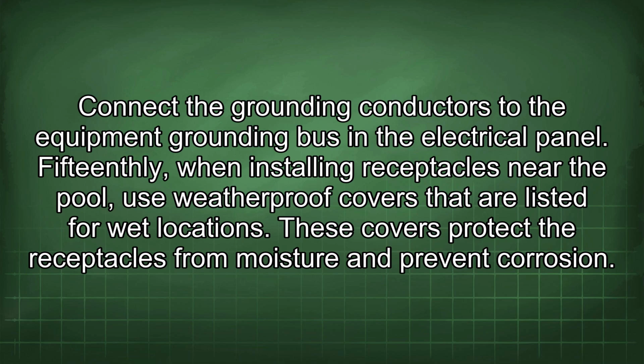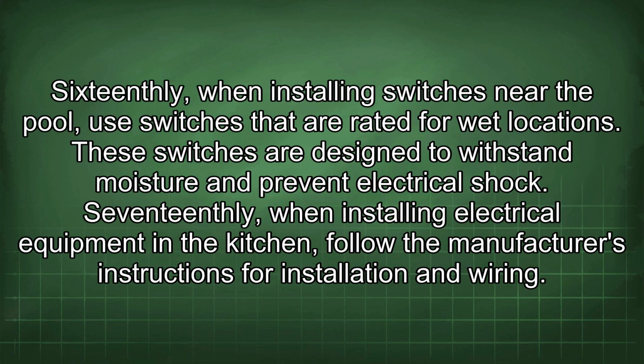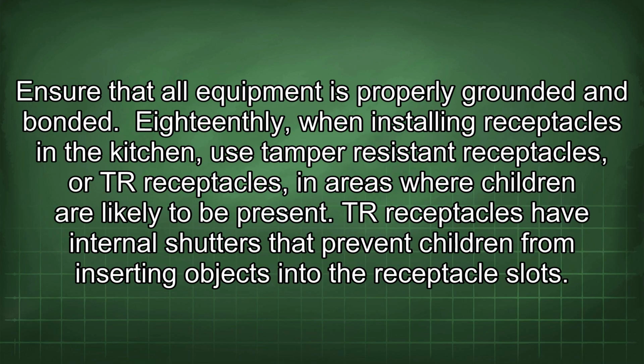15thly, when installing receptacles near the pool, use weatherproof covers that are listed for wet locations. These covers protect the receptacles from moisture and prevent corrosion. 16thly, when installing switches near the pool, use switches that are rated for wet locations. These switches are designed to withstand moisture and prevent electrical shock. 17thly, when installing electrical equipment in the kitchen, follow the manufacturer's instructions for installation and wiring. Ensure that all equipment is properly grounded and bonded.